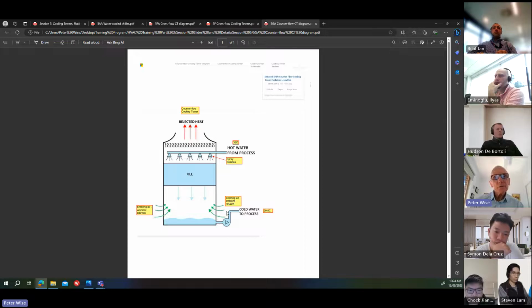There's also a counterflow cooling tower. I'll show you the diagram first. In this case, air comes in the bottom. The fill takes up the whole body of the cooling tower. So the air comes up from the bottom through the fill. In this case, the water is sprayed over the fill through these sprays. Now, when you're doing your pump pressure calculations, these sprays have a pressure drop, usually around 20 kPa. So be aware of that. If you're doing the pump pressure calcs and you've got a counterflow cooling tower, don't forget to allow for that.